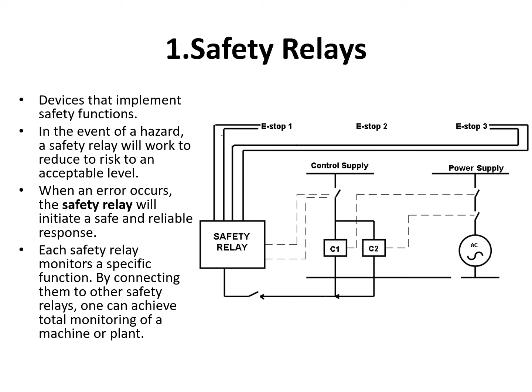The advantages of safety relays: they are cheap compared to other alternatives used for safety controls. They are simple and no software programming is required. Certain disadvantages of safety relays: wiring can be complex when the systems are very big. It's difficult to commission and fault finding is difficult when the system is down. Complete rewiring is required if changes need to be made later. These are the disadvantages.